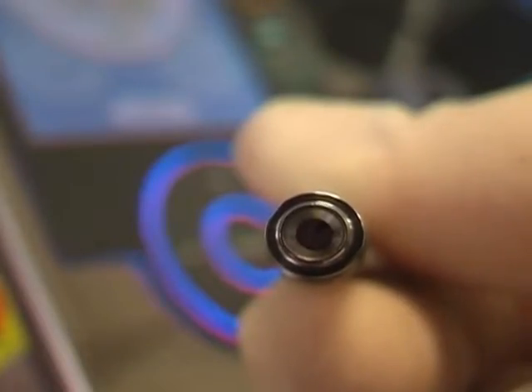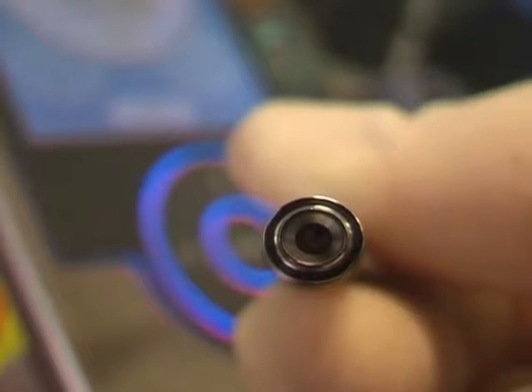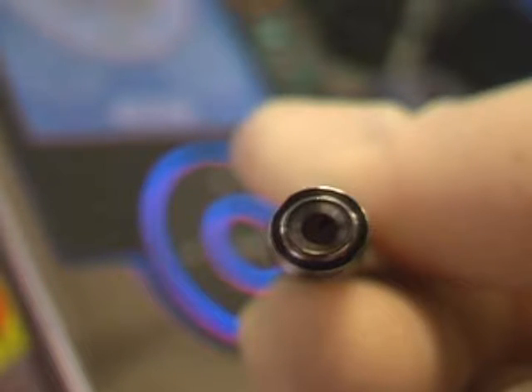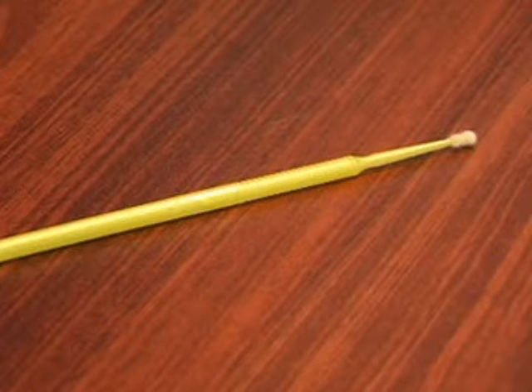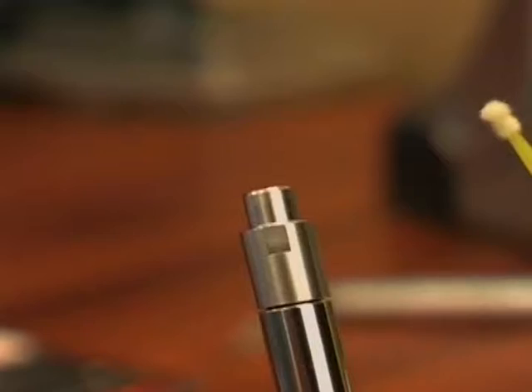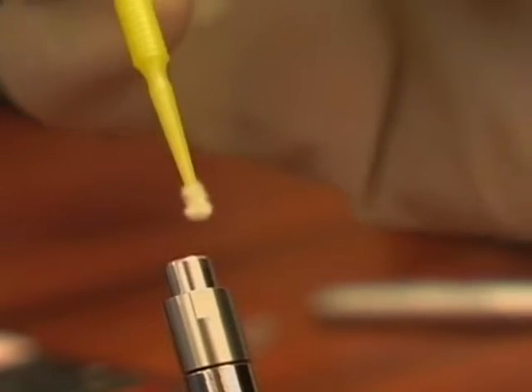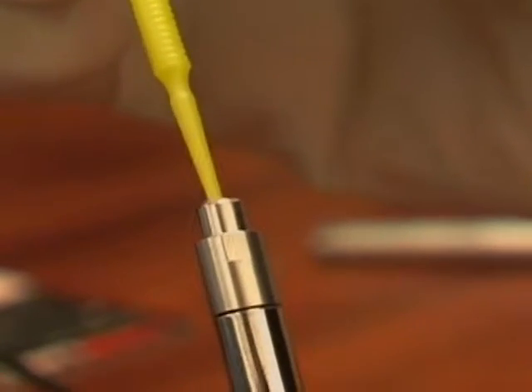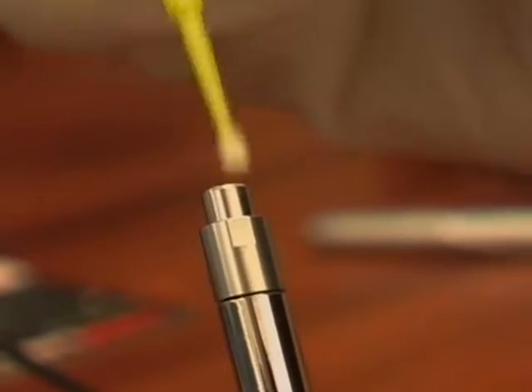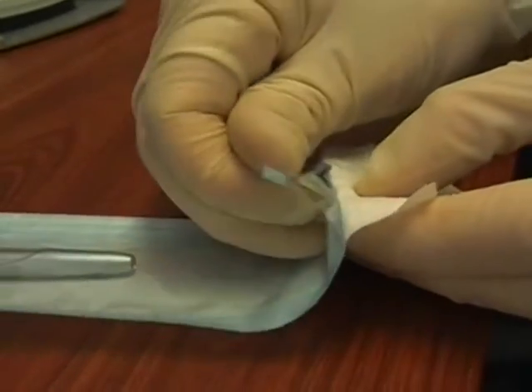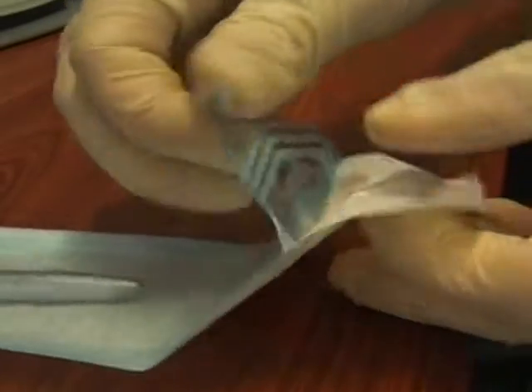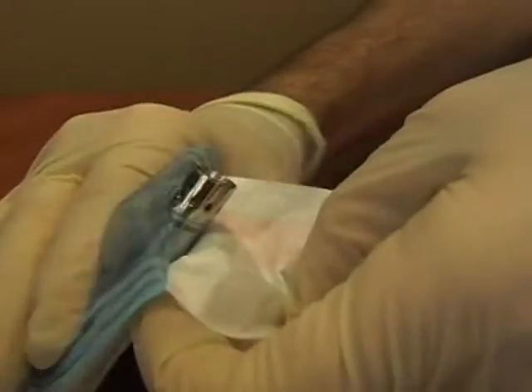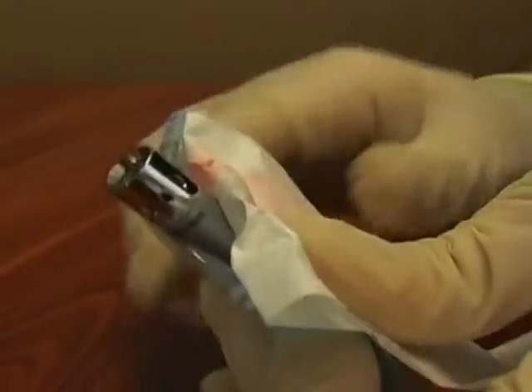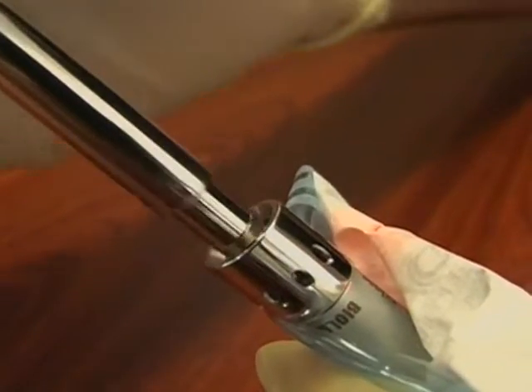Each time you replace a handpiece back on the shaft of the optical fiber, it is recommended that you visually check the window on the end of the fiber is clean and free of any dirt or dust that might have accumulated through normal use. If you see any contaminants, then you should clean the window with a microbrush as shown. This practice will greatly improve your unit's effectiveness and reliability. To replace the handpiece, remove from a sterilization bag, again with aseptic technique, and slide it over the optical fiber shaft, pushing it fully down until it engages.